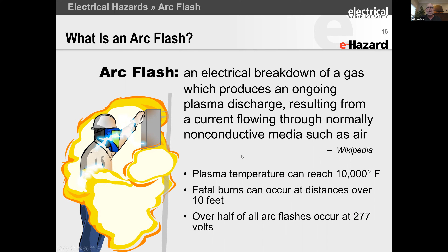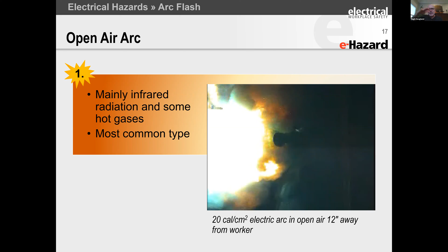This is an arc flash in an open air arc, and this is using our high-speed camera at the laboratory in Toronto. What you're seeing here is only half of the energy, because you're only seeing the hot gas ball. The energy in this particular arc is probably around 60% infrared and 40% convection. So the infrared is completely invisible. You can't see it, but it only goes in a straight line. That's why arcs are so focused, because you get a hot gas ball and infrared. The infrared doesn't go around curves or anything like that. So it usually only hits one side of the body, and it only hits in a fairly small area, depending on the arc flash.